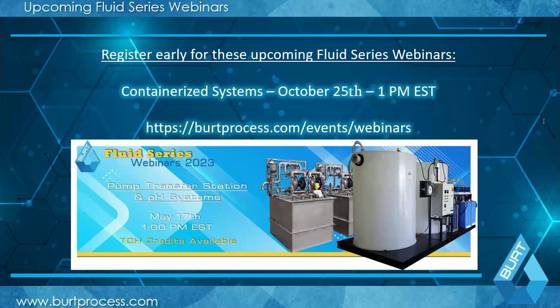A question here: what's the largest flow rate system that can go into a containerized design? So we're talking about containers. Most of them are based on standard Connex box design, which means you have an 8 by basically 40 feet as your maximum length. They do make specialty ones which are about 50 feet in length. And you can get a high Connex box, which is over 9 feet. A lot of times we do use the taller Connex boxes that go up to about 9 feet in height, I apologize.